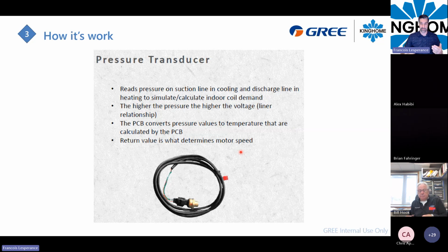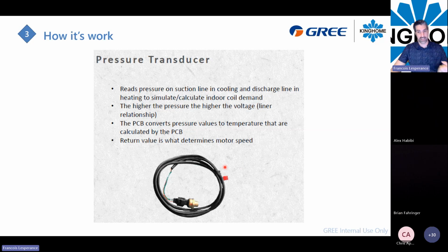So make sure when you do some test and service to not focus only on the pressure, because sometimes it can vary a little bit. So you will need a full picture of the system when you do some servicing on those kinds of units. So by knowing your outdoor temperature, your coil temperature, there's a lot of information you need to take from that unit before doing a service call on it.